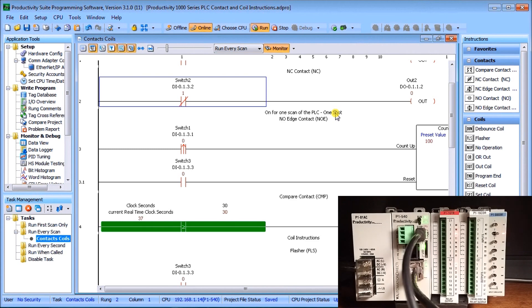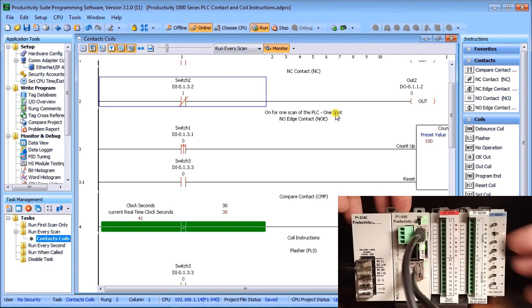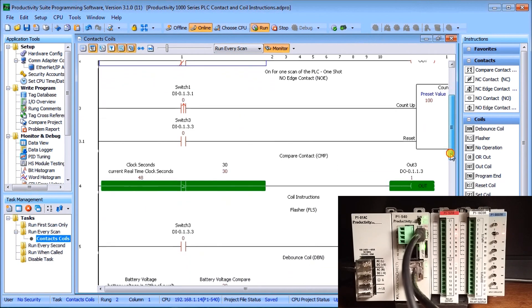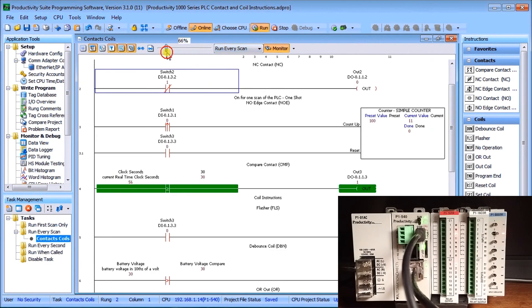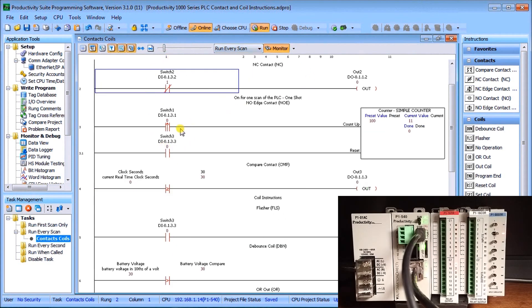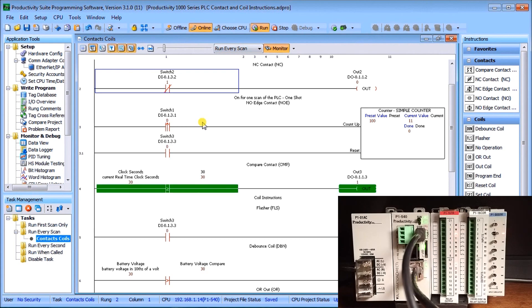The next instruction is a counter. We can zoom out a little bit to see what we're looking at. It's going off switch one — switch one then goes into a counter which is preset for 100, current value is 11, and the done bit is not on so it's zero. We use a normally open edge trigger, which is like a one-shot for our PLC. A one-shot will turn on for one scan of the PLC.